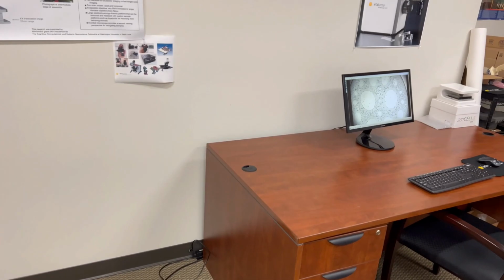In those cases where it's desired to have the user interface further than 10 feet from the incubator, we take advantage of the HDMI cable length having no limitations and use a Bluetooth or wireless keyboard and mouse. Here we've extended the user interface 34 feet from the microscope.